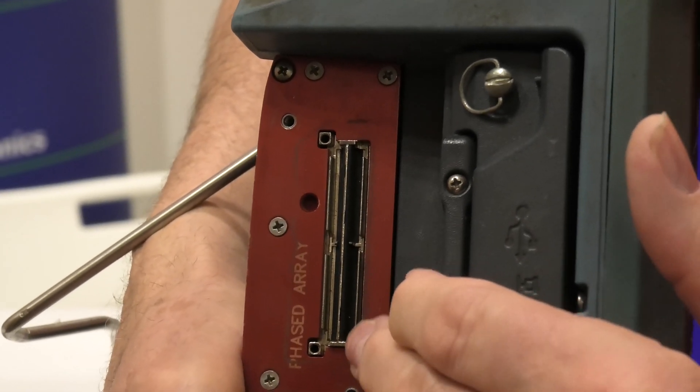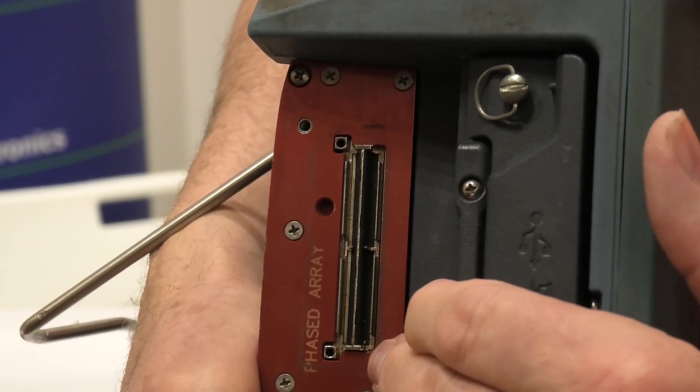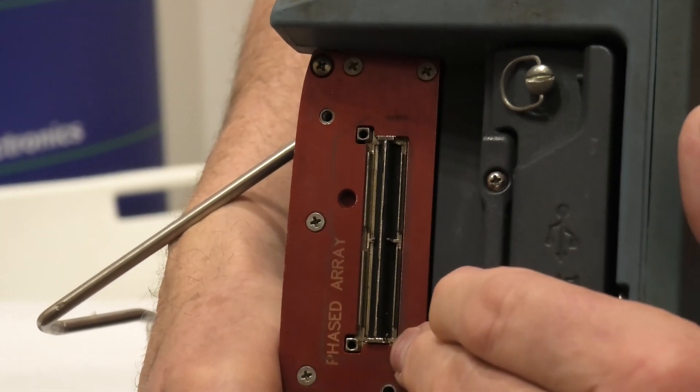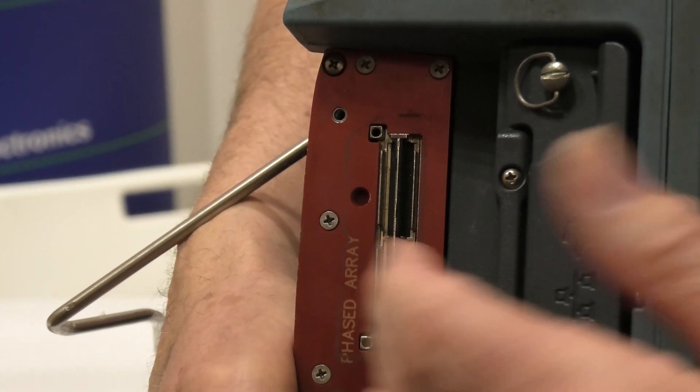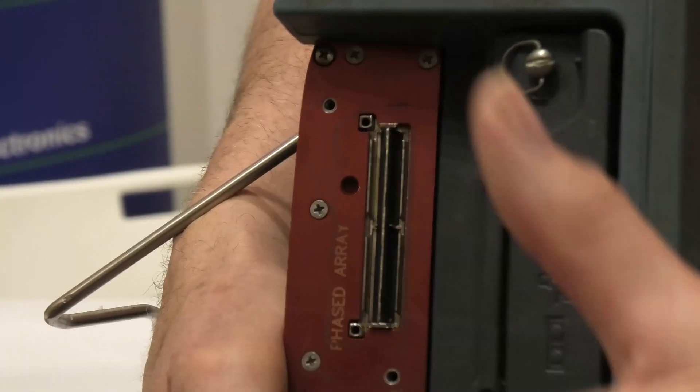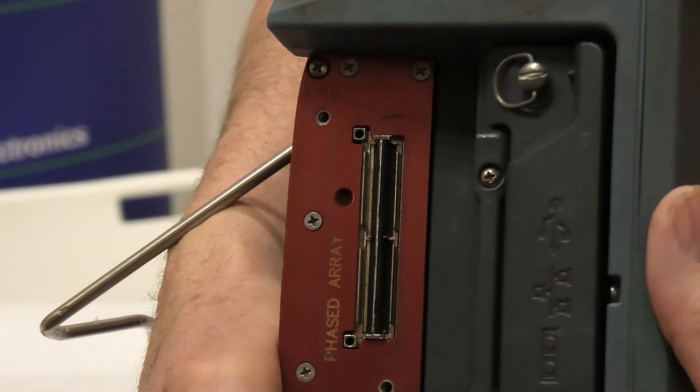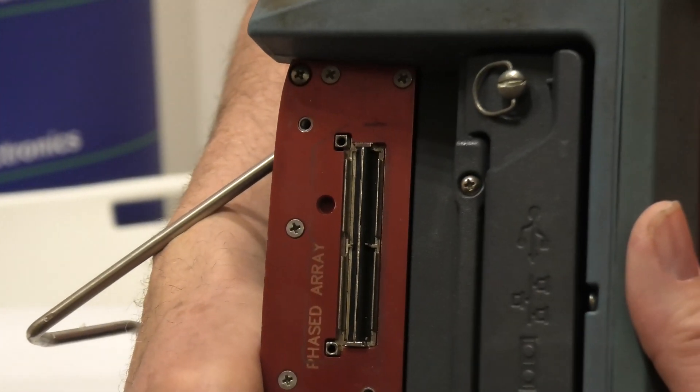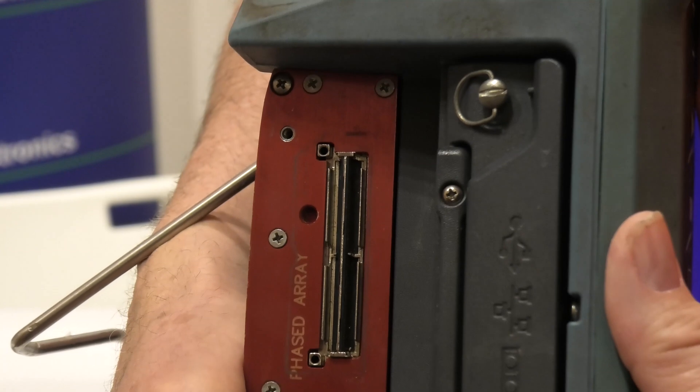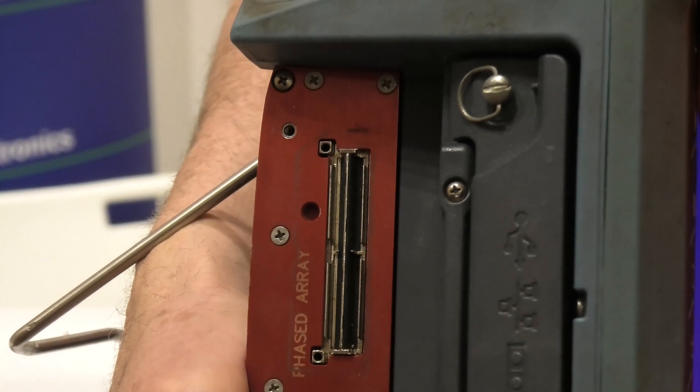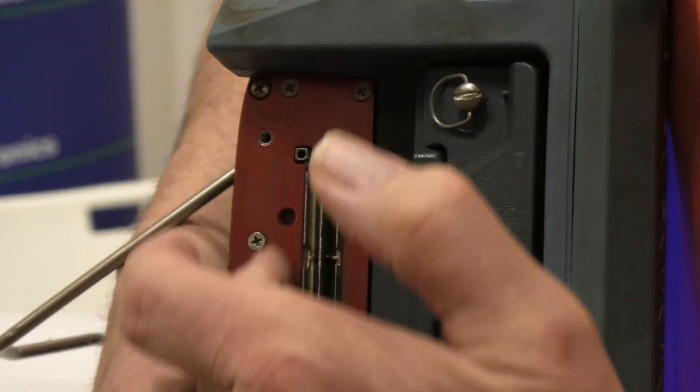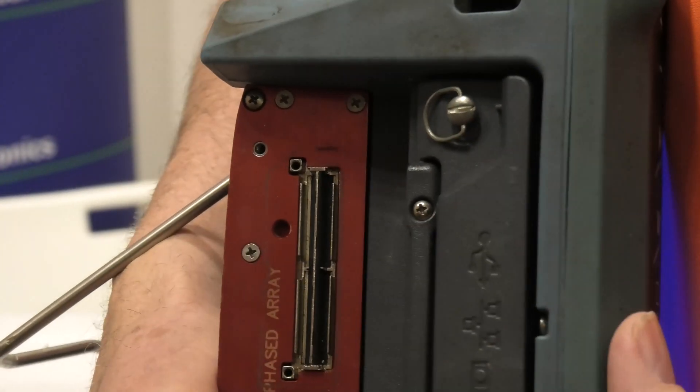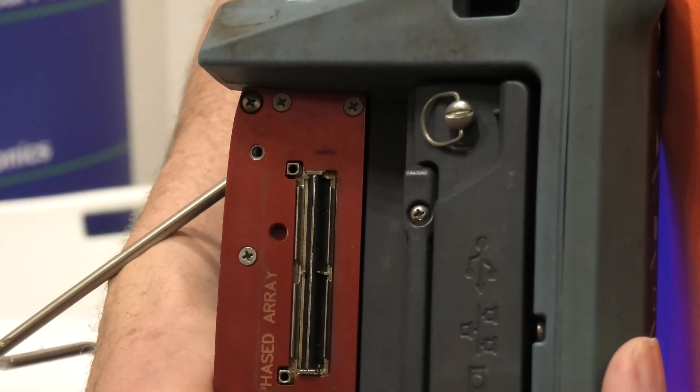So make sure the connector on your probe is in good condition. You connect it up and there's a simple test you need to run to confirm that we've got good connection all the way along from the phased array probe.